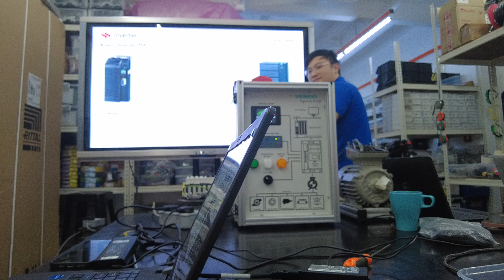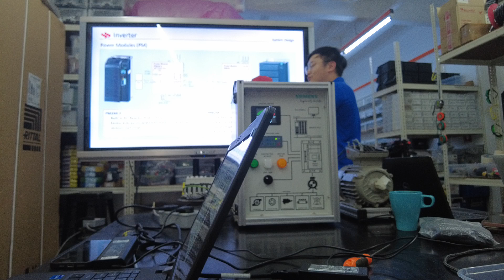Although current is there, the power becomes negative because the motor is driving the drive, so it acts like a generator and will generate a magnetic field. The backfeed current will backfeed to the inverter. Your inverter will try to do something to waste out the energy. If you don't waste it out, it will cause excess voltage on the inverter because too much voltage is generated from the motor, so we have to fine tune the motor or use some external component to protect it.